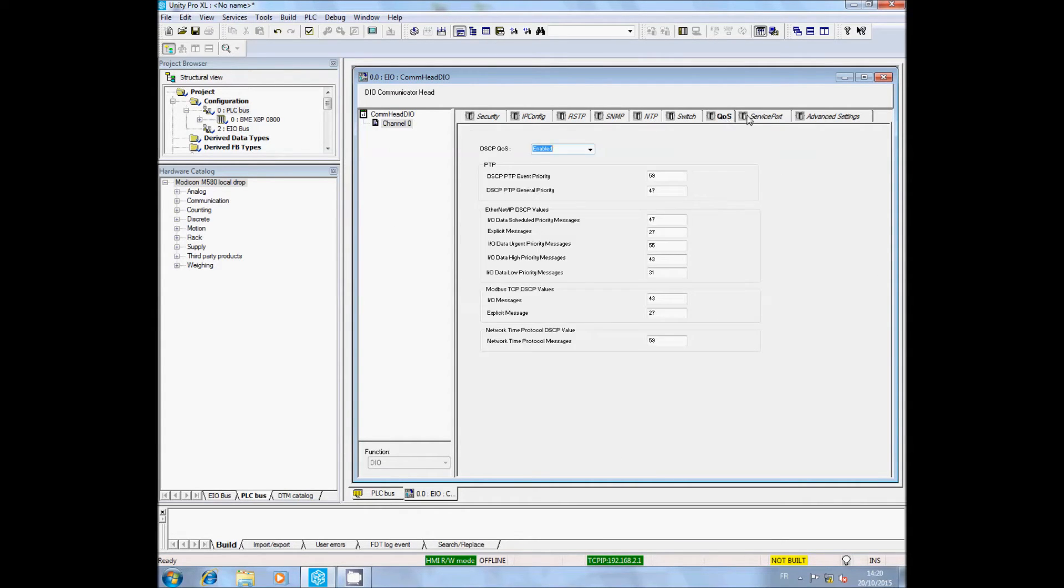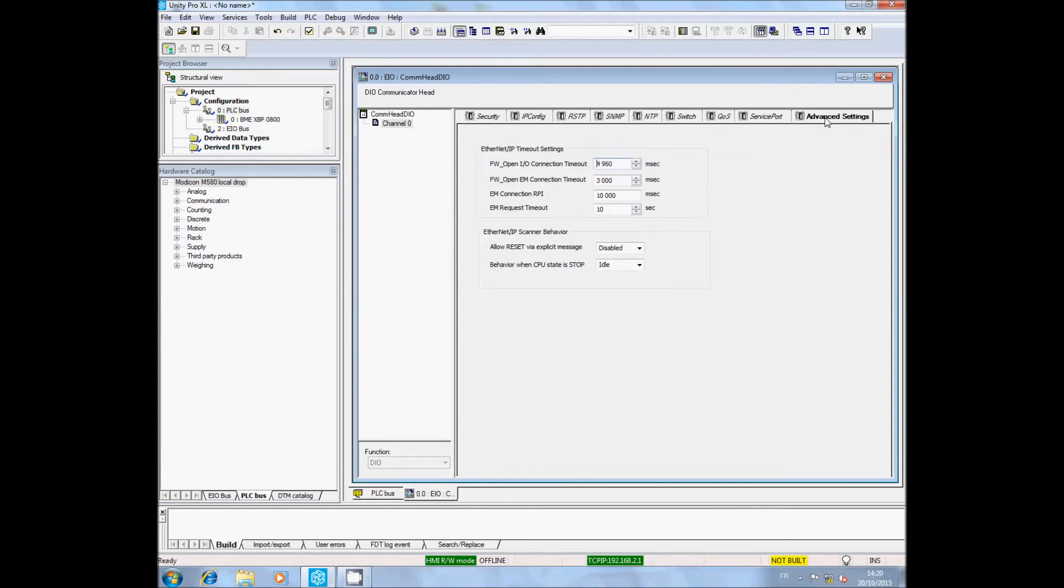In the Service Port tab, check that the service port is enabled. Have a look at the other tabs to be sure they match with your project. Close the window and save the modifications. If you want, you can build the program and transfer it into the PLC.